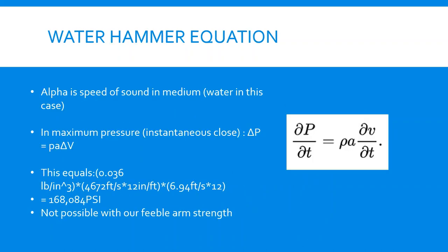Here's the water hammer equation. Note that alpha is the speed of sound in water. Assuming that we can instantaneously close the valve, the maximum pressure we can get is delta P equals rho times alpha times delta V. Plugging in numbers, we get about 170,000 psi, which is not possible with our current conditions.